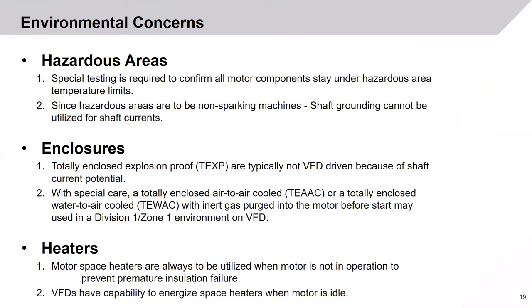For hazardous areas, specifically Division 2 or Zone 2 areas, special testing is required to confirm all motor components stay under the hazardous area temperature limits for that given gas or dust. Since those areas are supposed to be built as non-sparking machines, shaft grounding cannot be utilized for shaft current. For Division 1 or Zone 1 areas, totally enclosed explosion-proof motors are typically not VFD driven because of shaft current potential. However, with special care, a totally enclosed air-to-air cooled (TEAAC) or totally enclosed water-to-air cooled (TEWAC) motor with an inert gas purged into the motor before start may be utilized in Division 1/Zone 1 environments and can be driven by a VFD.